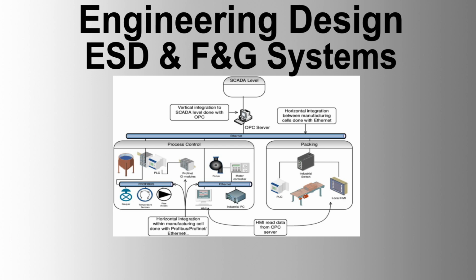2. Installation and configuration documentation. Step-by-step installation guides must be provided to ensure proper setup of the system hardware and software. Configuration manuals detailing the setup and customization of the ESD F&G system must be included. 3. Testing and validation documentation. Test plans and procedures for factory acceptance testing, FAT, and site acceptance testing must be provided. Test reports documenting the results of all testing activities, including performance tests, integration tests, and validation tests, must be included.